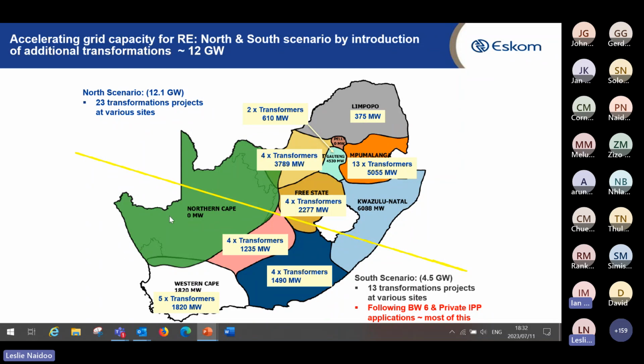In the Northern Cape, following bid window 5 and 6, we've actually run out of network capacity—meaning the transfer limits out of the Northern Cape have been exhausted, whether due to thermal constraints or substation transformation constraints. This means there's a limited amount of transmission network available to evacuate or dispatch that power to load centers elsewhere in the country.